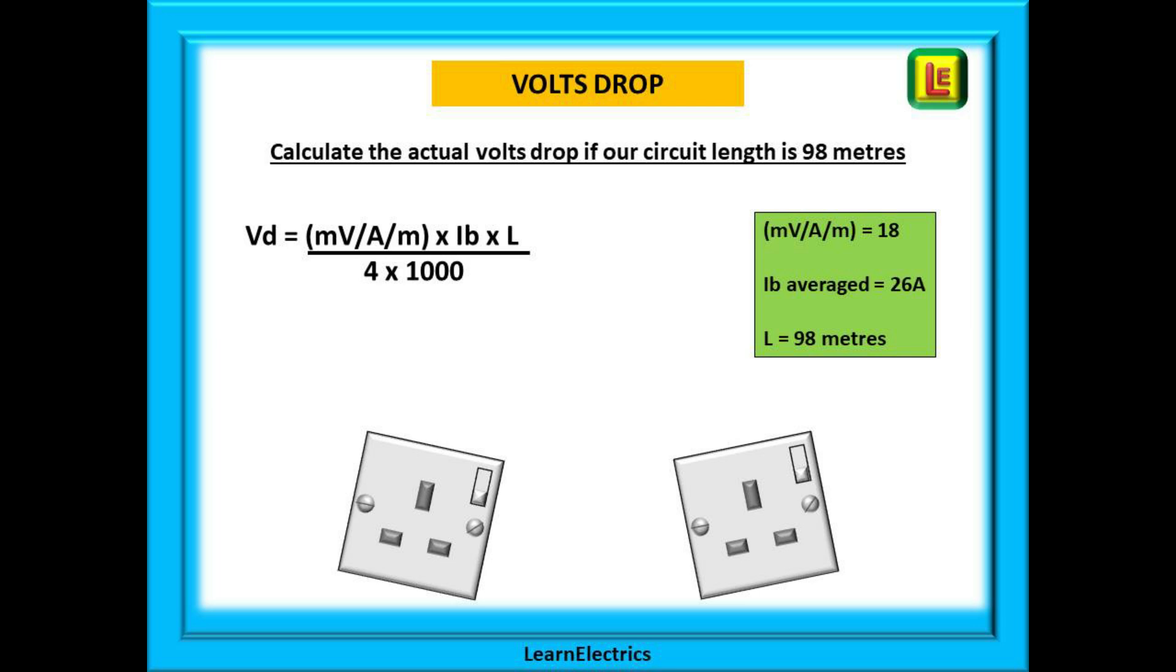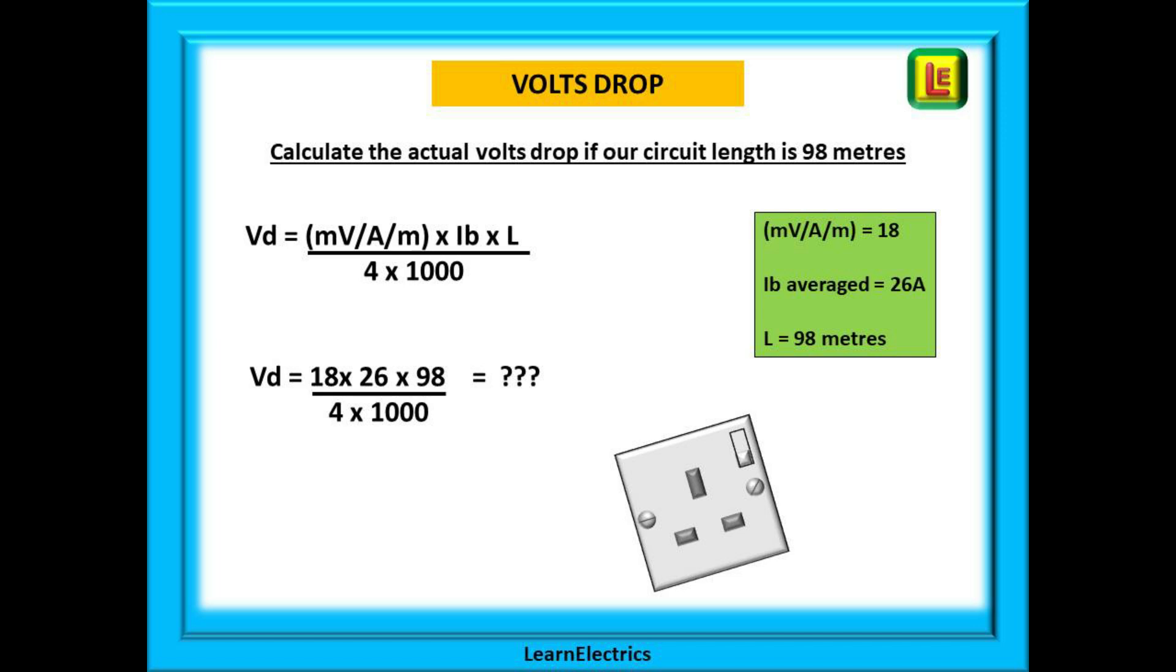The data to enter is shown in the green box. We have put the numbers into the formula. Now we just need a calculator and out pops our answer, 11.47 volts. A 98 meter ring circuit in 2.5 millimeter twin and earth with an average load current of 26 amps will have a voltage drop that is just inside the permissible maximum.